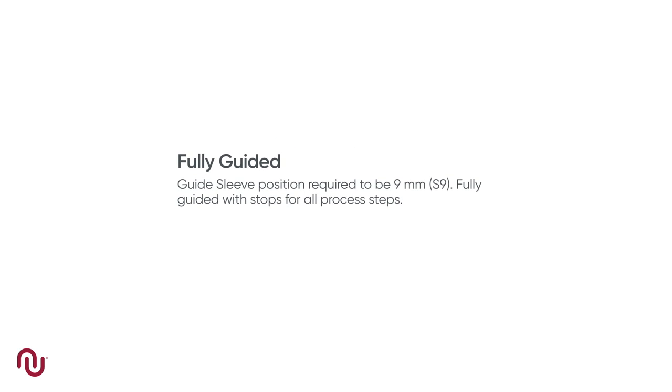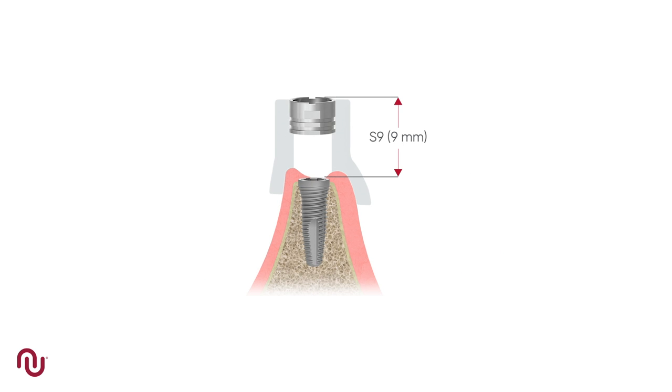Fully guided means that all steps in the process, be it drilling, countersinking, or implant placement, are done to hub. To hub means coming to a complete stop. This option can only be used in conjunction with a sleeve position of 9mm, indicated by the value S9.